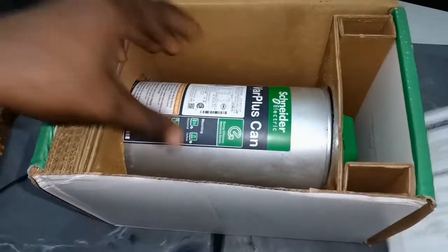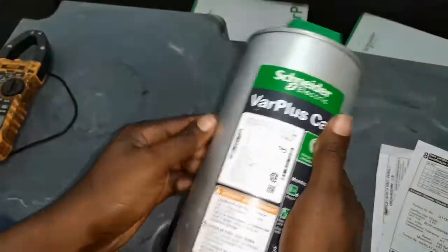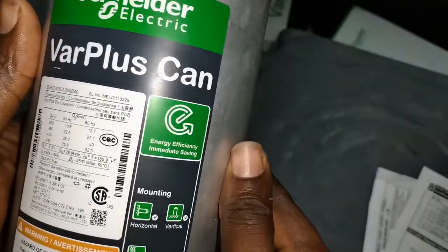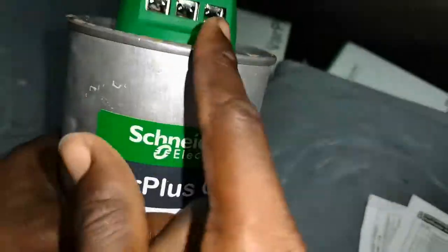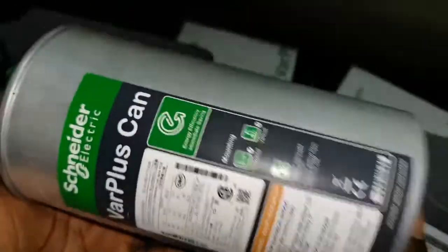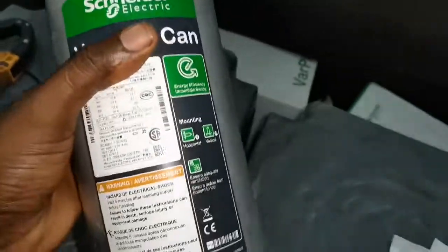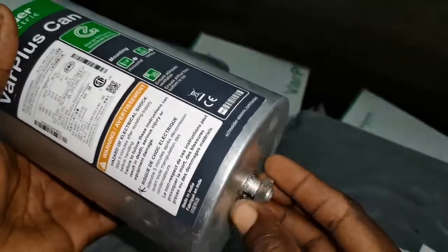This is a Varplus Can three-phase capacitor and it is a 25kVAR capacitor. It is delta connected, which is why you have the three terminals and the earth or ground. You can easily install this in the horizontal form or in a vertical form, and this place hooks to the earth or the ground.